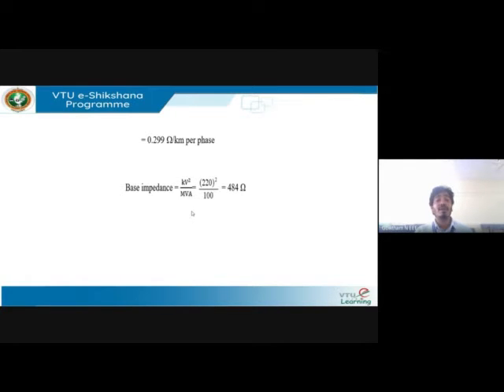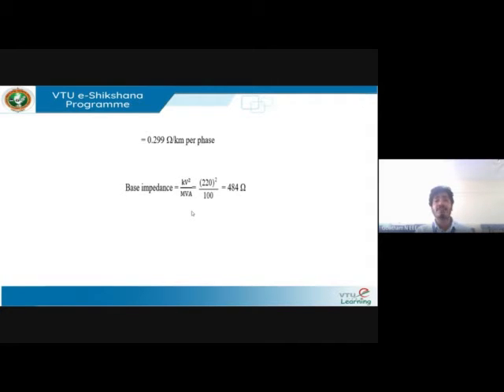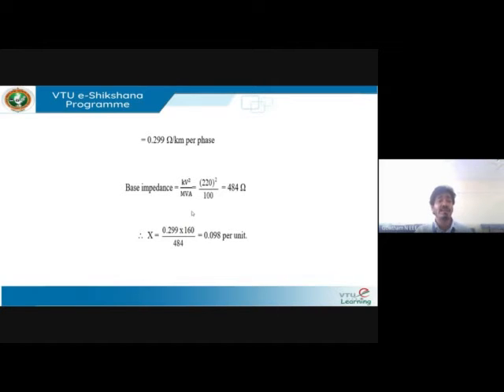They also ask for the per-unit reactance. The base impedance is calculated as 484 ohms using the given base of 100 MVA at 220 kV. The per-unit reactance X = (0.299 × 160) / 484, where 160 km is the line length, giving a per-unit reactance of 0.098 per unit.